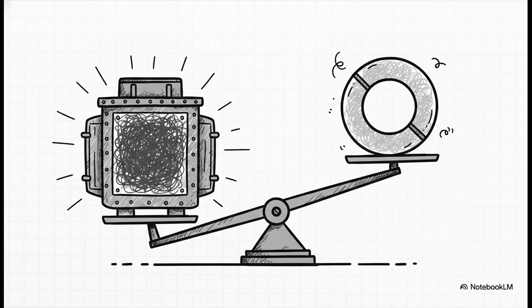Metering applications do not require a C-class CT. Remember our fork in the road earlier between metering and relaying? Well, those bulky, expensive C-class ratings are strictly for protection purposes, so they can handle fault currents. If you just need revenue metering, stick to metering class CTs. They're typically much smaller, significantly less expensive, and they're going to save you a ton of space.